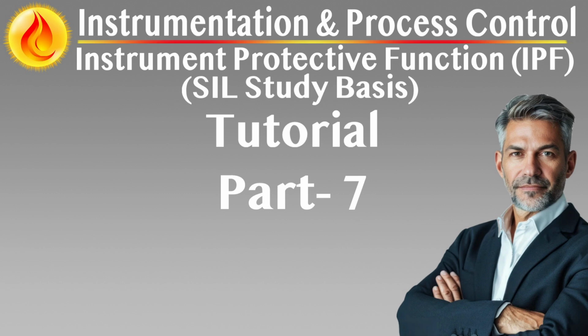Operator interaction and restrictions. Read-only access for operations. Operators must be able to view override status but should not be able to apply or remove maintenance overrides unless specifically authorized. Activation and deactivation must remain restricted to qualified maintenance or instrumentation personnel through secure access.